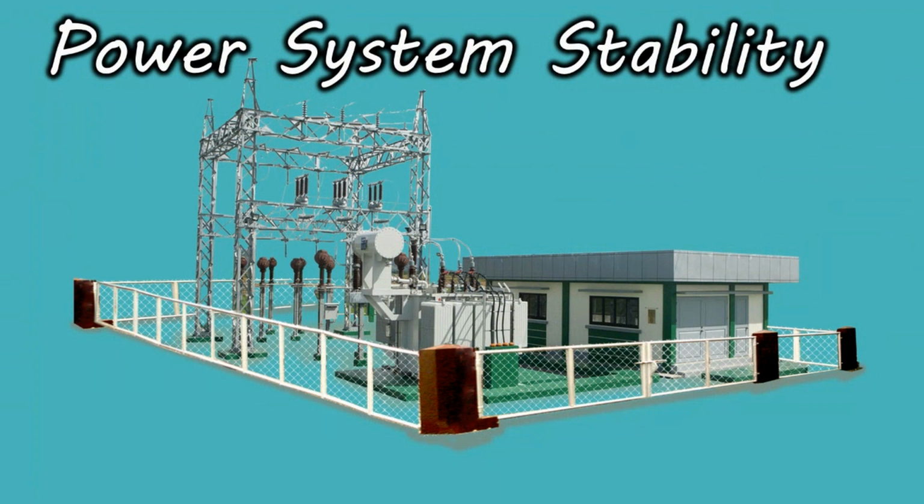You saw the design; we have to make a balance between energy and vibration. Like when we have a wave, a vibration, an oscillation, there is energy transmitted with this wave. If you leave it, it will destroy your conductor. Providing this damper, which you are asking about, will convert this energy to motion of the two sides of the damper, or to heat or something else. It will take the energy from this wave outside the conductor.